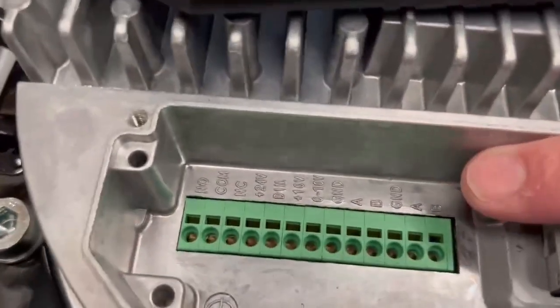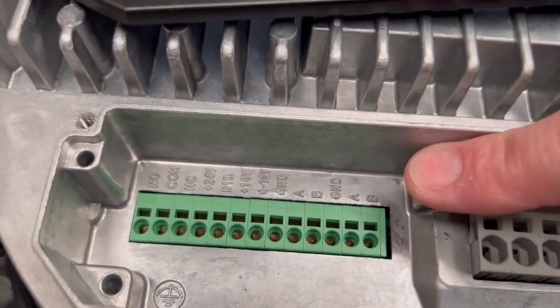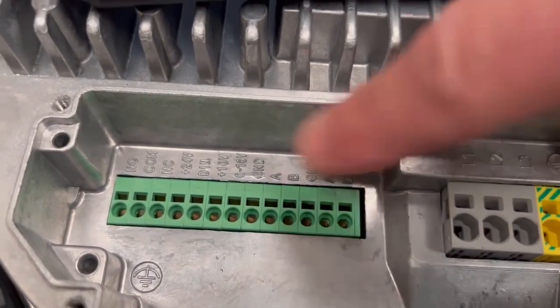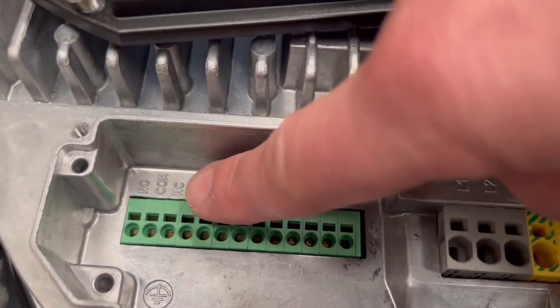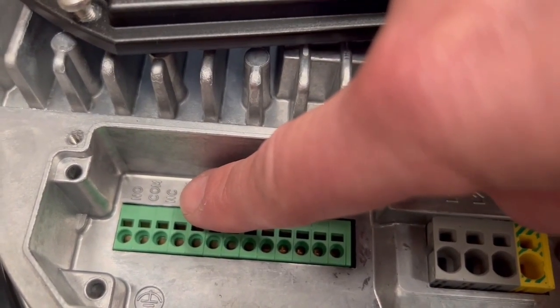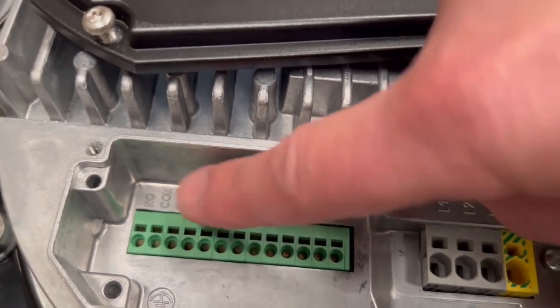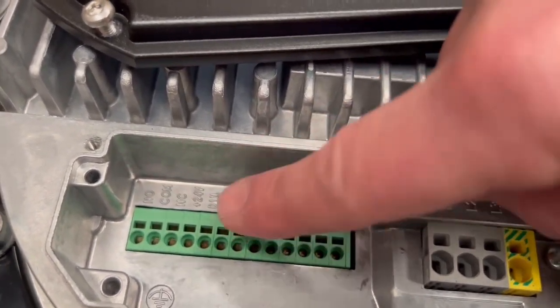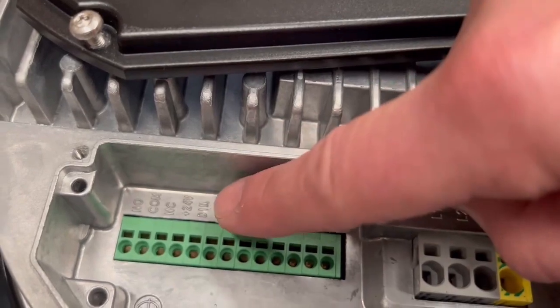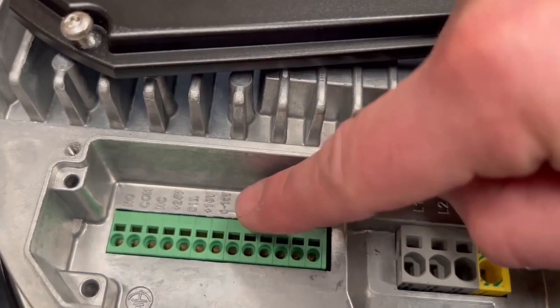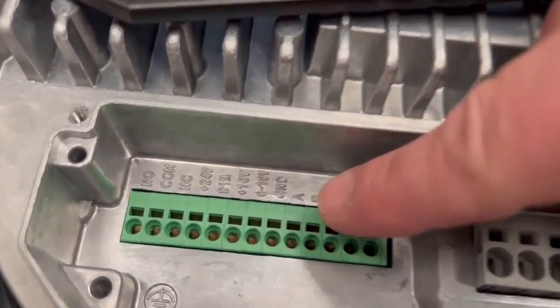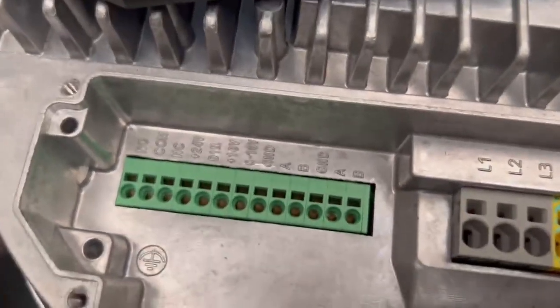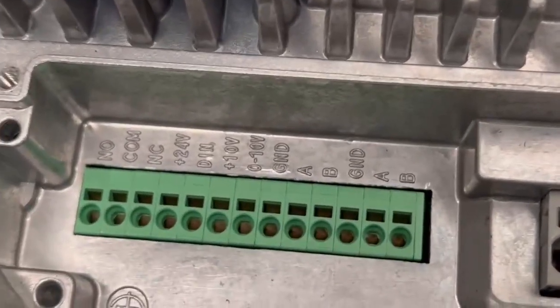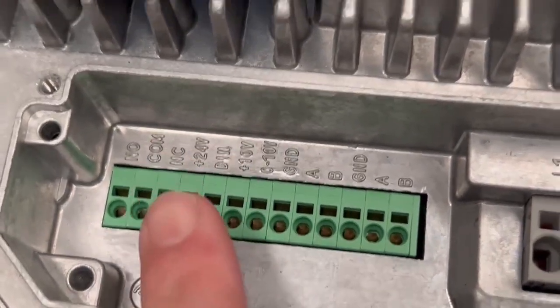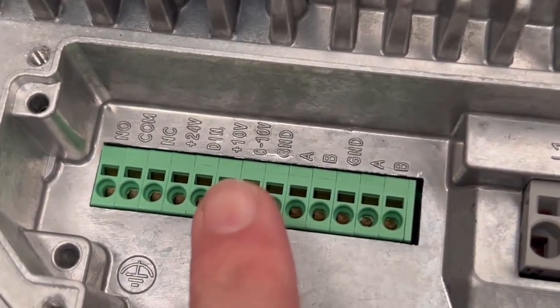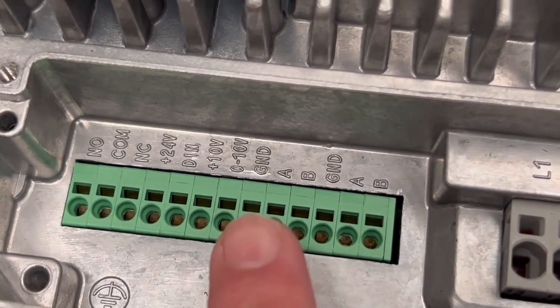On the side here where we have the inputs, these are normally closed and common. These could be voltaged or low voltage. So just be careful when you're applying these connections that you don't mix them across here, because you can burn out the fan if you put 230 volts on these 0 to 10 volt and low voltage connections. If we zoom right in, we can see we have a 24 volt connection, a digital input, a 10 volt supply, a 0 to 10 volt and a ground.